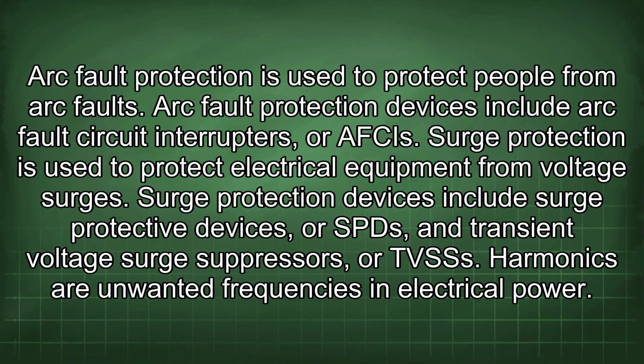Arc fault protection is used to protect people from arc faults. Arc fault protection devices include arc fault circuit interrupters, or AFCIs. Surge protection is used to protect electrical equipment from voltage surges. Surge protection devices include surge protective devices, or SPDs, and transient voltage surge suppressors, or TVSSs.